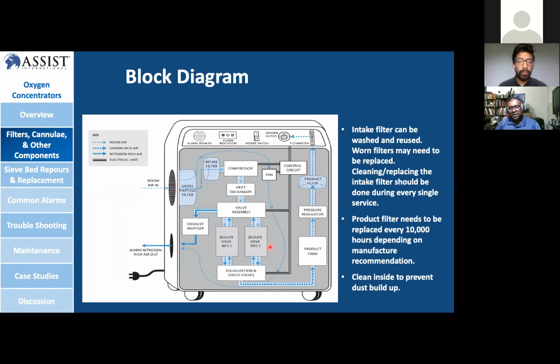Looking at the block diagram again, you get room air going into the system and through a filter, and from the filter to the compressor. From the compressor, it goes to the heat exchange and valve assembly that switches that line to zeolite 1 and zeolite 2, and you have an exhaust muffler. When the switching happens, one of the zeolites releases the unwanted gas out again. During the switching, the equalizer check valve changes and sends oxygen to the product tank.